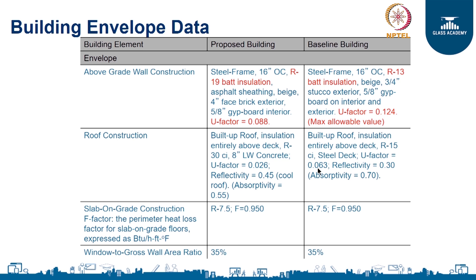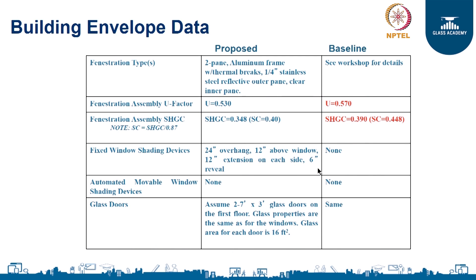We document the various aspects of the envelope and the different material properties for both the baseline and the proposed case. The proposed case is reflective of the actual building post-construction, where you put in the actual elements you want in the design. In the baseline case it is programmed to the code depending on the energy code you want to adhere to. Most baseline codes like ECBC or ASHRAE 90.1 try to limit the window-to-wall ratio to 40 percent.